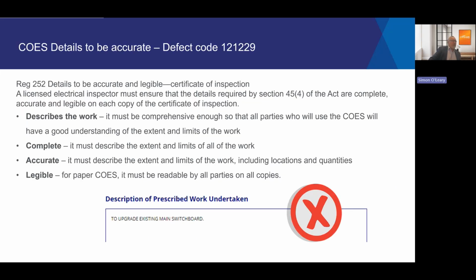Another common defect that is issued is insufficient information on certificates of electrical safety. The legislation says that information on or the description of work on a certificate of electrical safety needs to be complete, accurate, and legible. If you're using electronic certificates of electrical safety, legibility is probably not too much of a concern, but the information needs to be complete and accurate.